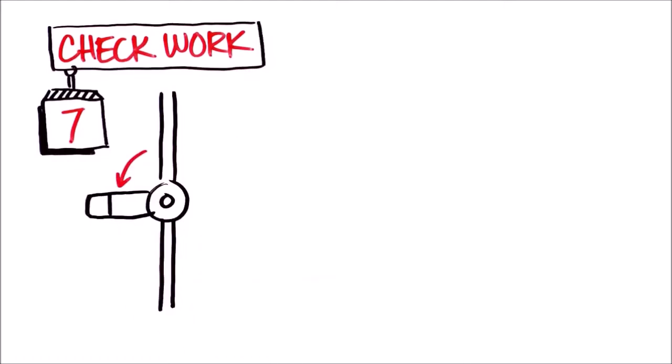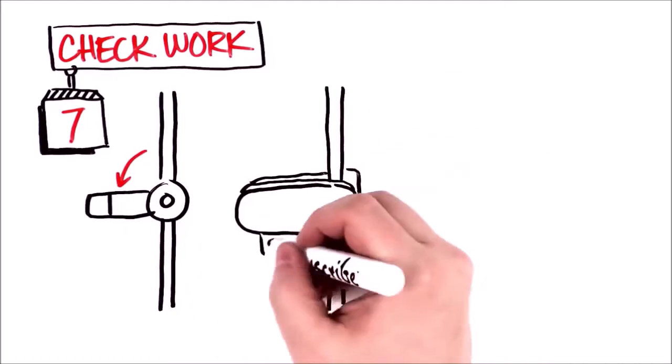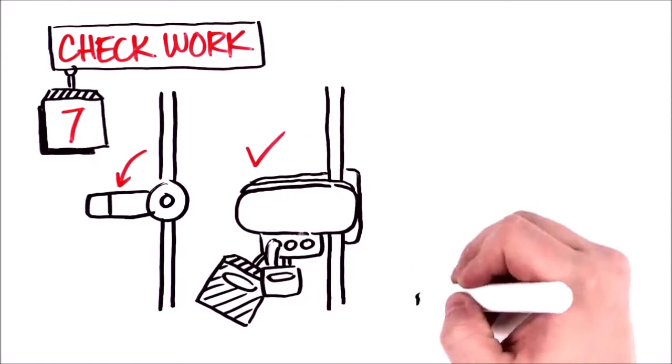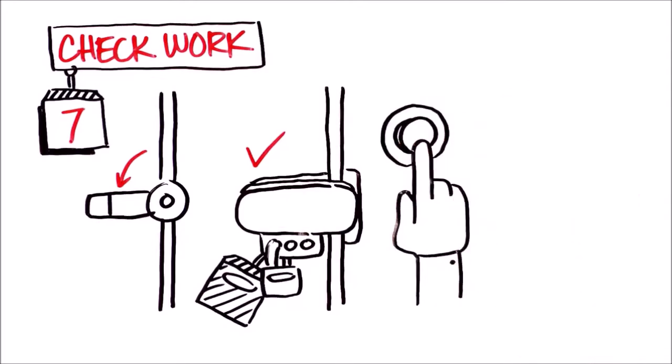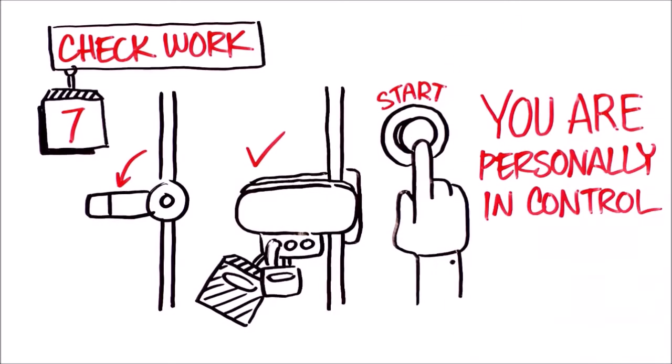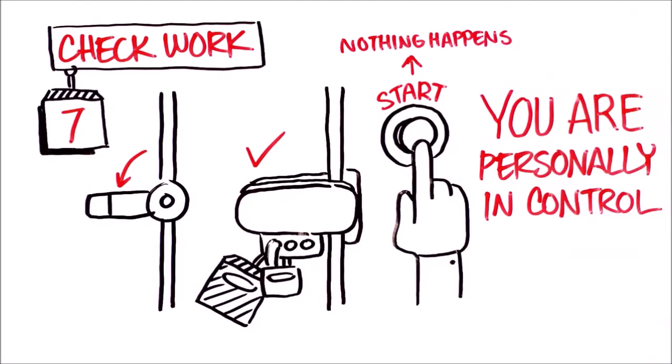This step is important. Check your work. Try it out. Verify that each step so far has been done correctly. That means that after properly doing a LOTO procedure, you confirm that all energy sources are isolated with a physical barrier. You verify that the equipment will not restart, and you are personally in control of the hazardous energy that ensures that equipment can't restart without your awareness.